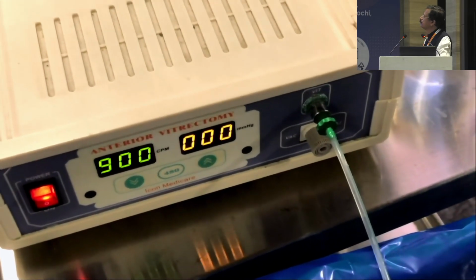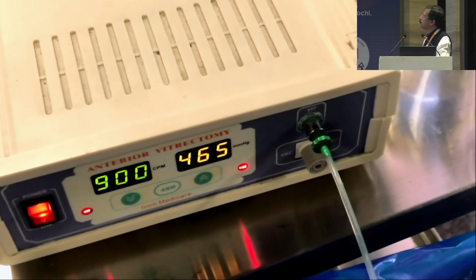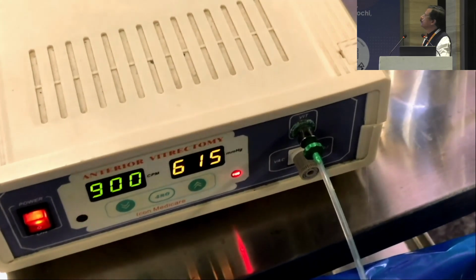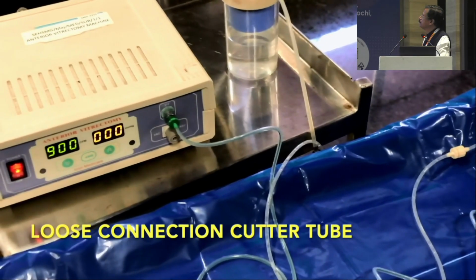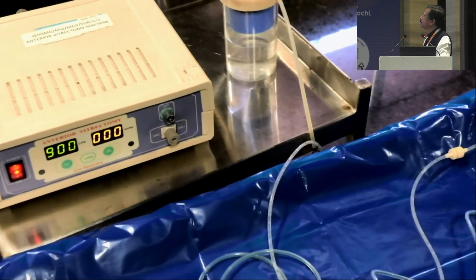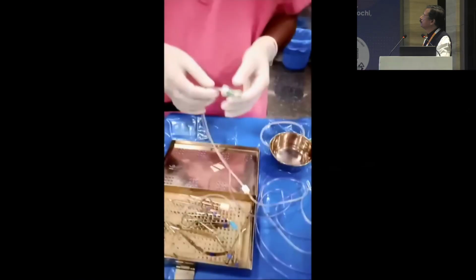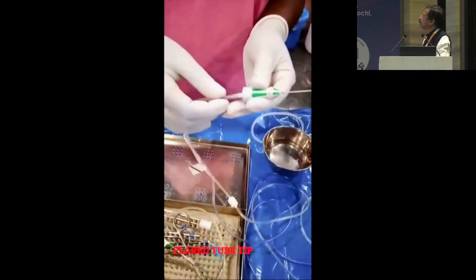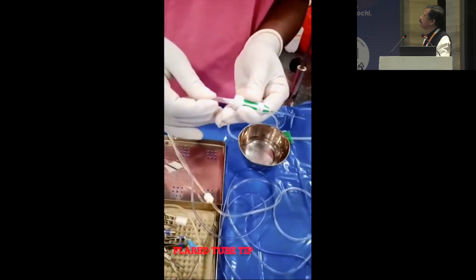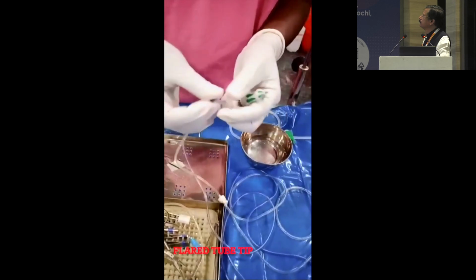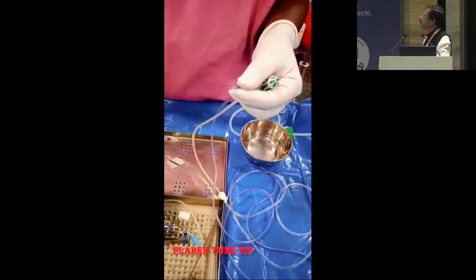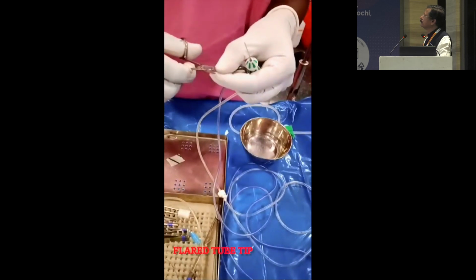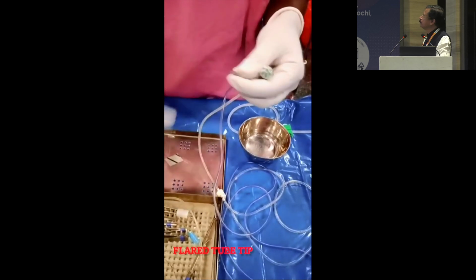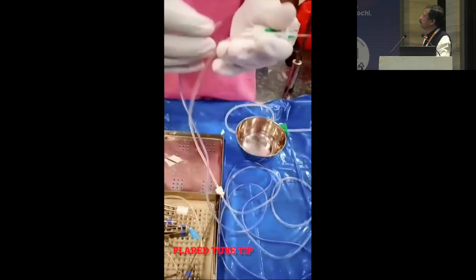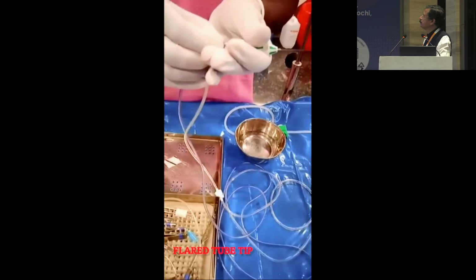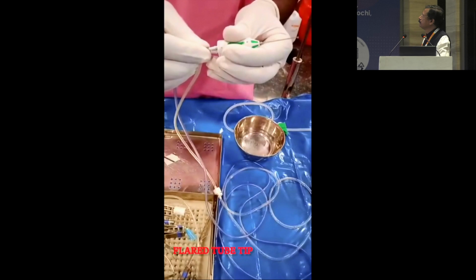Now the vacuum is slowly building up. So if you connect the vitrectomy tubes loosely, when you press on the push pedal, it will suddenly come off. Sometimes the vacuum won't generate. When you look at the vitrector, the tubing looks fixed, but the tip may be flared up. At that time, the small jugaad you can do is cut the tip with scissors and refix it. So now it will be snugly fixed and it will generate normal vacuum.